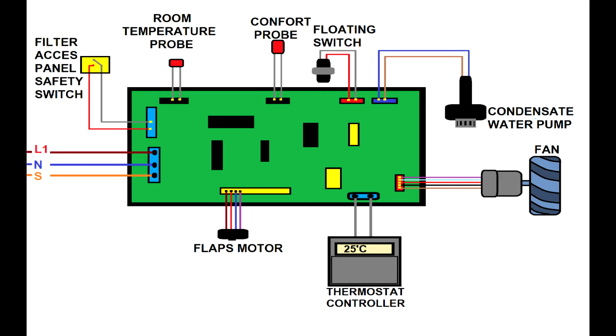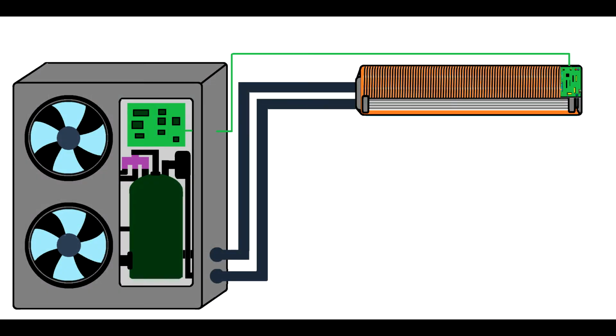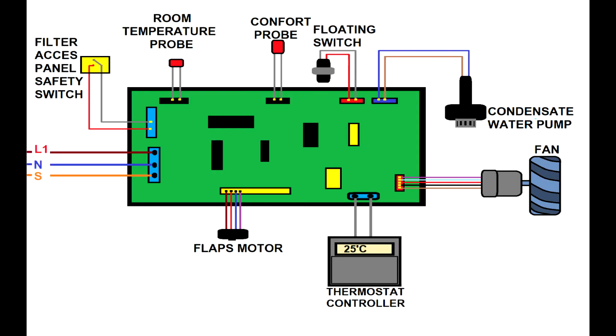If you look into the indoor, you have to be careful. You have the room temperature probe, comfort probe, floating switch, condensate pump, fan, thermostat, flaps motors. All these things, you have to wire them correctly, and then you can use it for everything you want. By looking into this picture, what you will observe, the indoor has a printed circuit board. That printed circuit board from the indoor, which you see on the right hand side on the top, controls the outdoor. So if you have the remote control, you will instruct the outdoor to start.